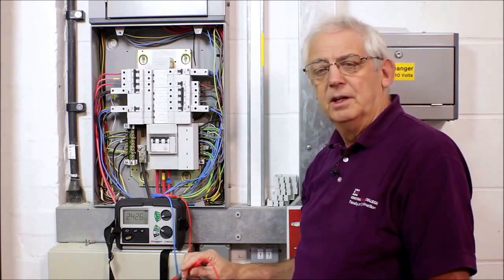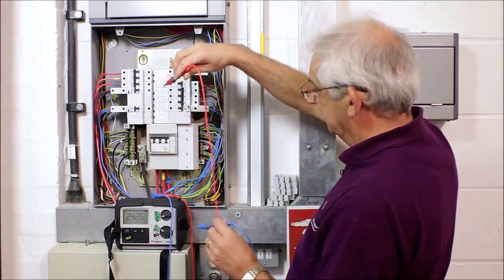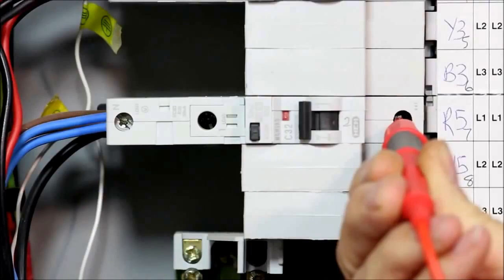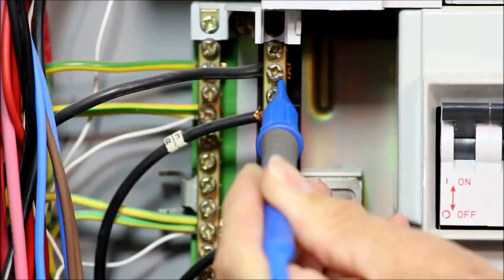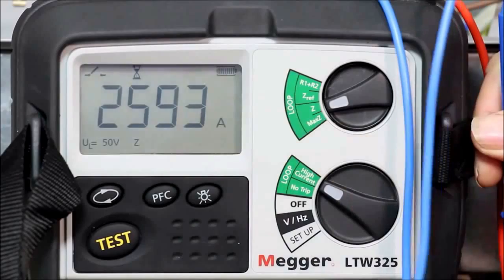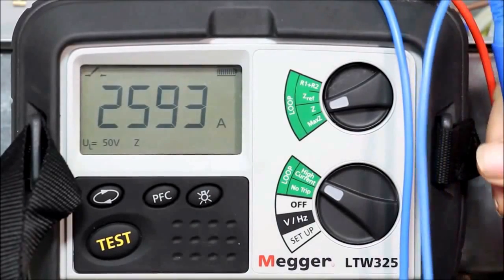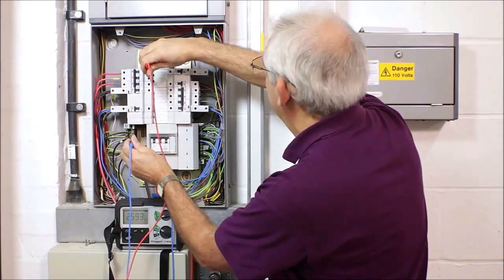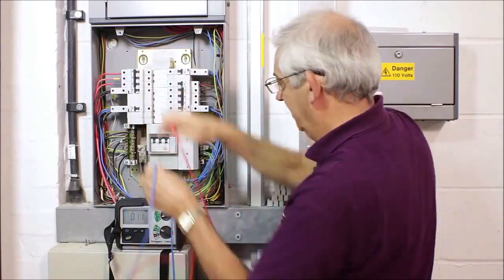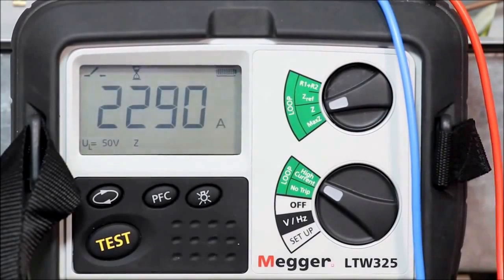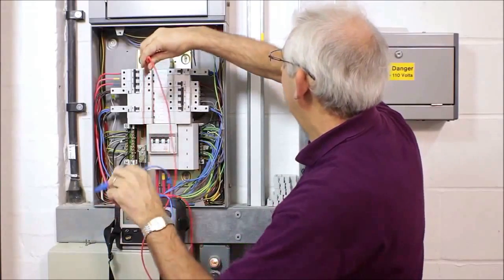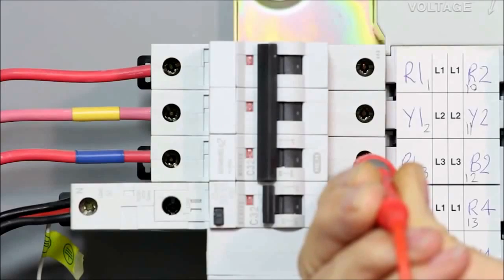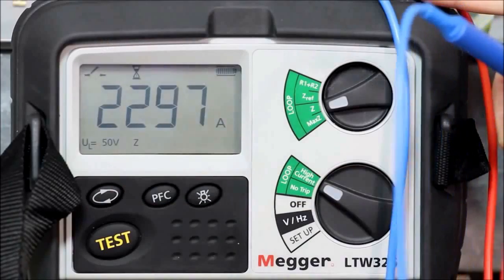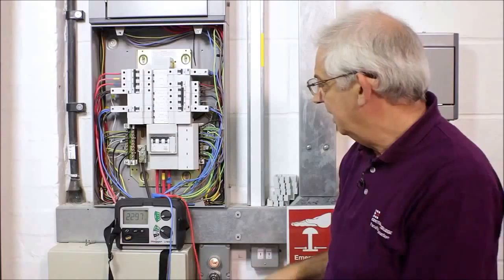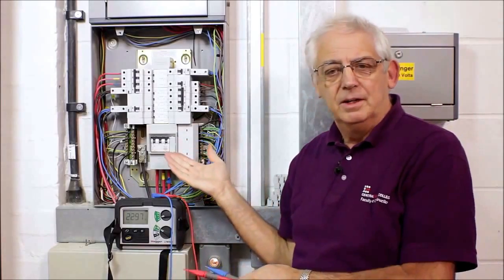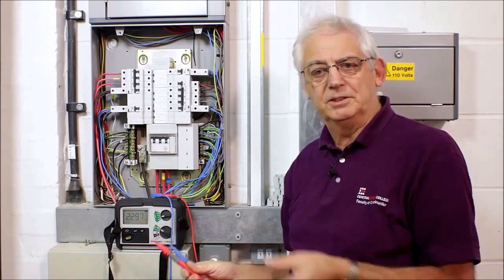Next, I need to measure between line and neutral. Again, all lines to neutral, so I'll go on L1 first, or the red phase in this case. Take a reading, push the button, 2,593. Now between the yellow and the neutral, push the button, 2,290. And now between the blue and the neutral, push the button, 2,297. Now, because this is a 3-phase supply, obviously current that could flow between 2 phases would be much higher.